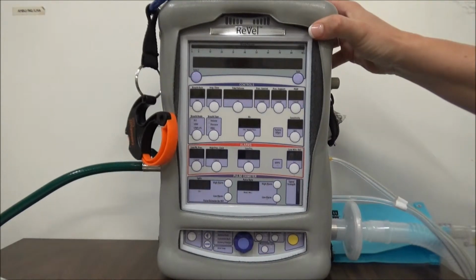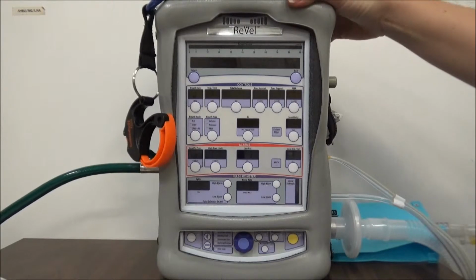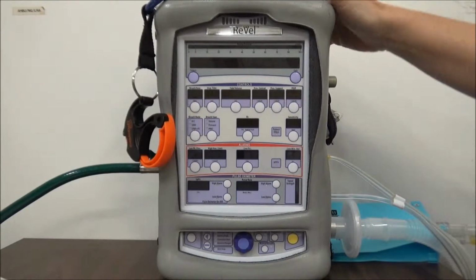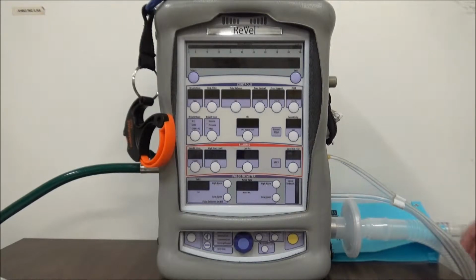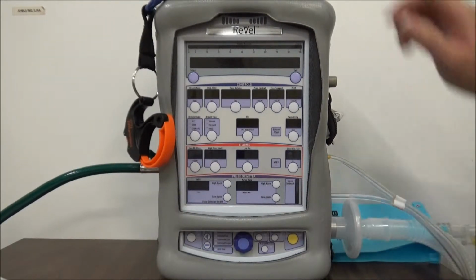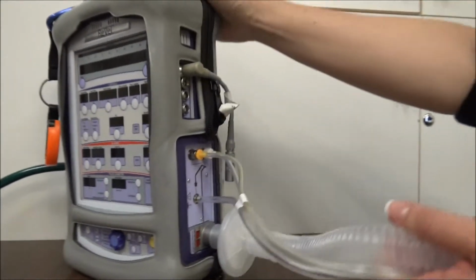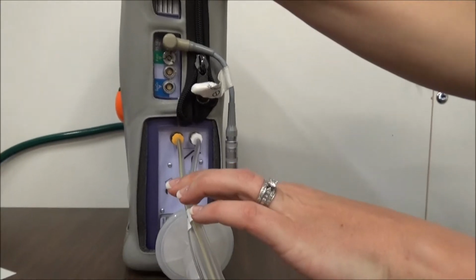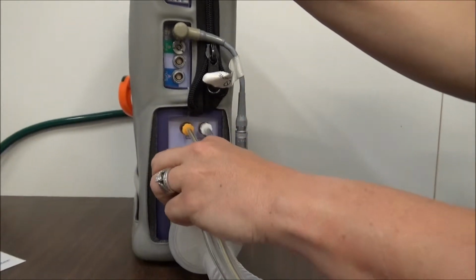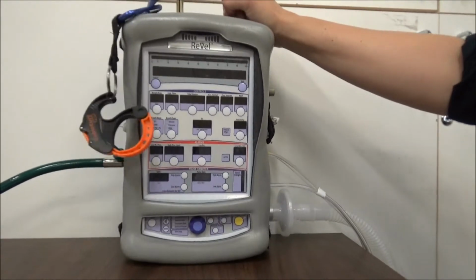Alright guys, today we're going to set up the ventilator in SIMV PRVC mode that we use here at MedEvac for most of our transports. So the first thing I've done is picked my adult circuit that's over here. I've put on my bacterial filter and I've put in all three of my pressure lines. And just make sure those are on there really tight. Those will generate some pretty big alarms for you if they're not.